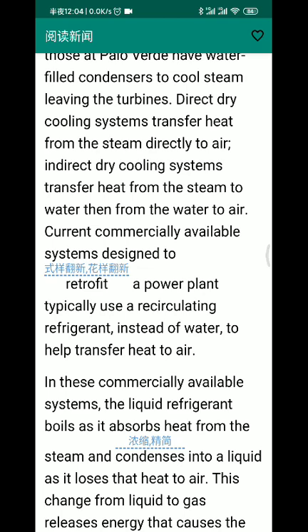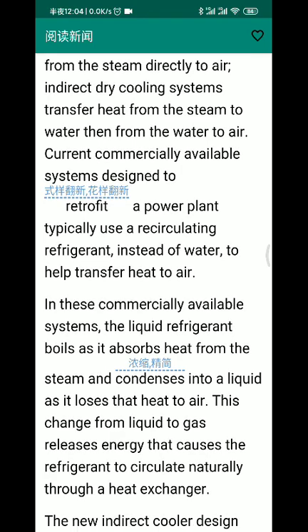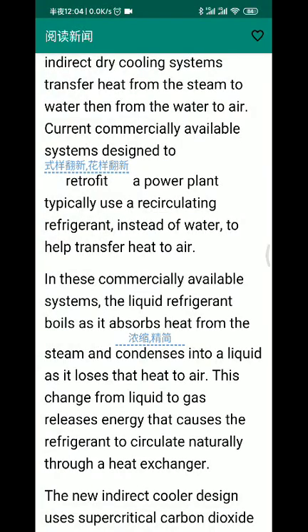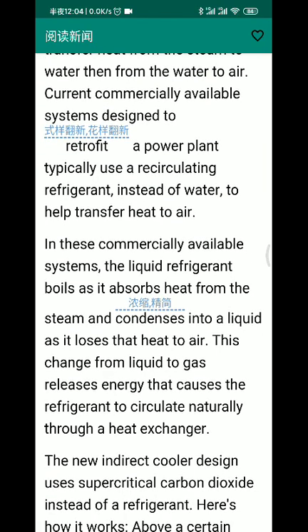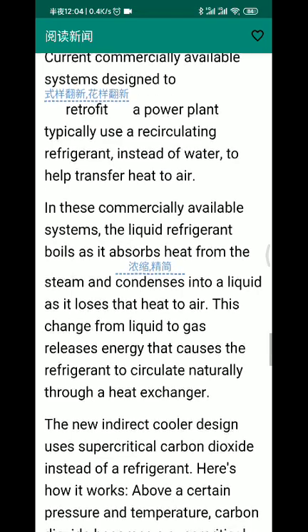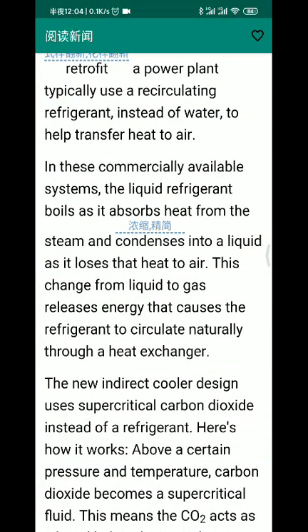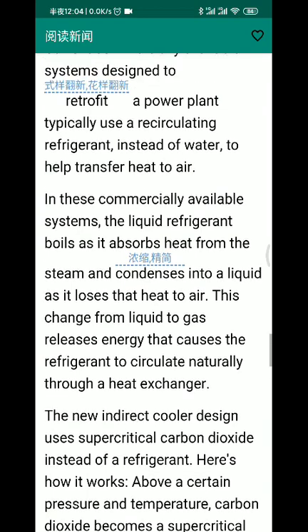designed to retrofit a power plant typically use a recirculating refrigerant instead of water to help transfer heat to air. In this commercially available system, the liquid refrigerant boils as it absorbs heat from the steam and condenses into a liquid as it loses that heat to air. This change from liquid to gas releases energy that causes the refrigerant to circulate naturally through a heat exchanger.